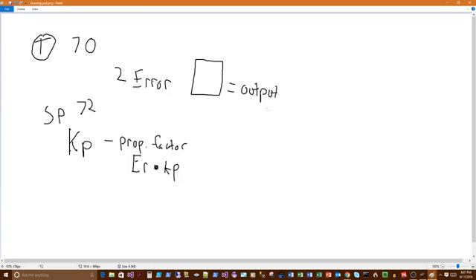Because our output is then going to go and drive our little VAV box here and our little damper actuator. So that might be damper output, right? And our output is going to drive this damper output based on this error. So over time, this error, which is now giving us an output of 4%, because let's say our KP is also 2. It equals 2. So 2 times 2 is 4. We've got 4% output.